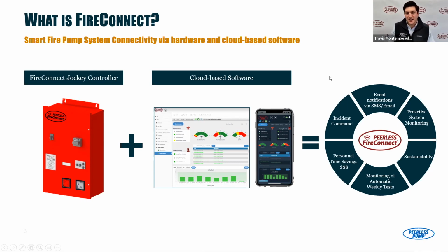It enables things like sustainability. So we'll talk a little bit about water savings. Monitoring of your weekly tests, so code compliance for running your required weekly or monthly fire pump test, for example. Logging that information automatically as the test is running, being able to look back at that from a historical standpoint. So if you're required by your AHJ or your service provider and you need to send that information, that's all captured automatically. So you just share a PDF, send that to whomever is asking for that information, and boom, you're compliant effectively.